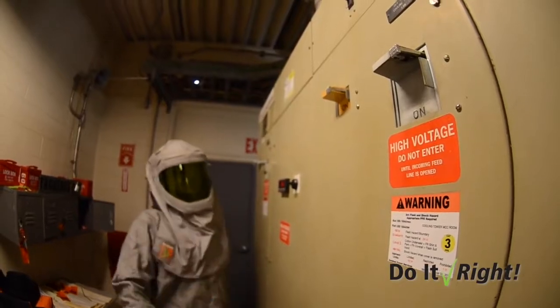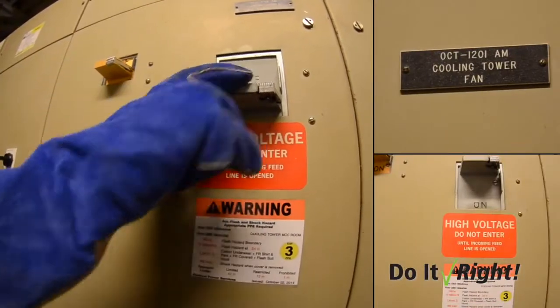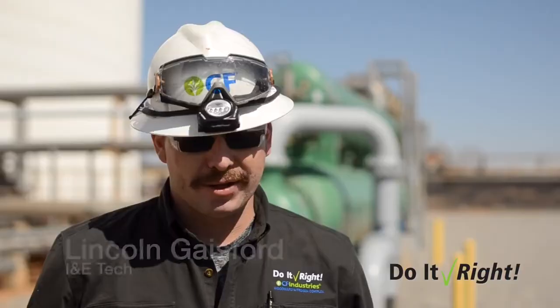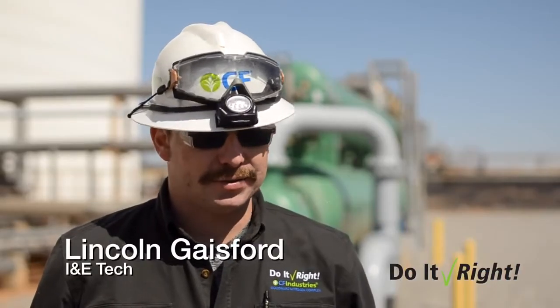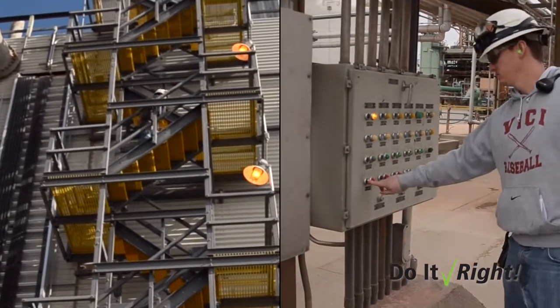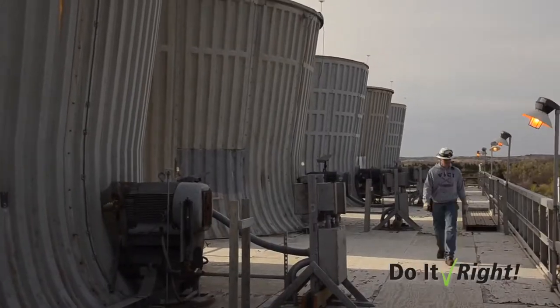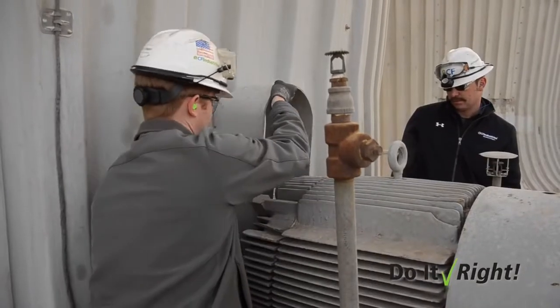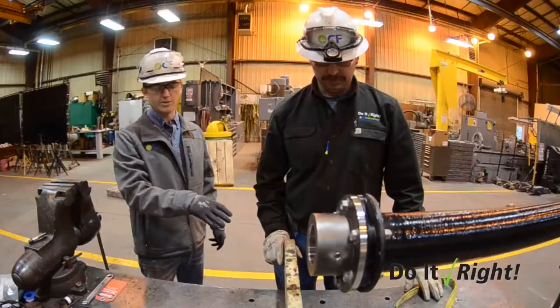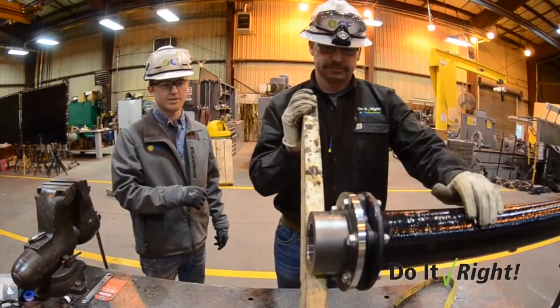We were called in to replace the cooling fan on one of our cooling tower motors. We did our normal lockout, tagout before we went up there. We had to take the cover off the back of the motor to gain access to stop the rotation of the shaft.